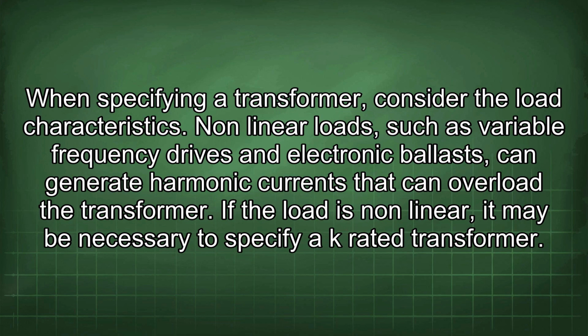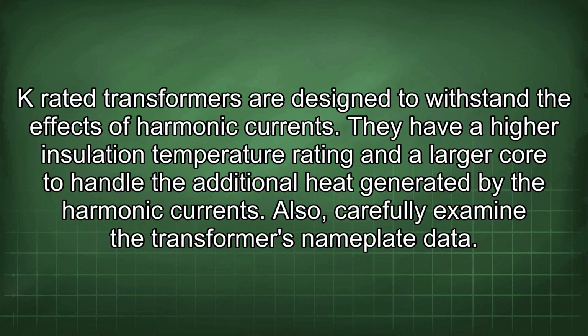When specifying a transformer, consider the load characteristics. Nonlinear loads, such as variable frequency drives and electronic ballasts, can generate harmonic currents that can overload the transformer. If the load is nonlinear, it may be necessary to specify a K-rated transformer. K-rated transformers are designed to withstand the effects of harmonic currents. They have a higher insulation temperature rating and a larger core to handle the additional heat generated by the harmonic currents. Also, carefully examine the transformer's nameplate data.